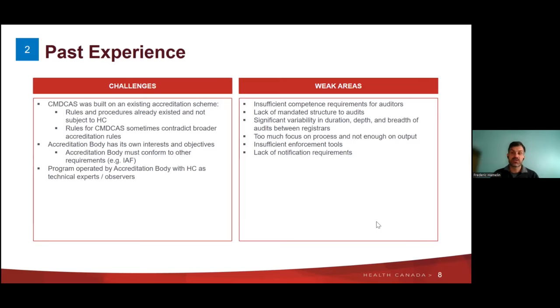The other advantage was because it could be combined relatively easily with the auditing activities required, for instance, for marketing authorization in Europe. It was a lot easier, I think, for manufacturers, because now they didn't need some sort of separate audit or inspection for Canada. It could be rolled into one with the CE marking audit. So that was, I think, advantageous for both parties.